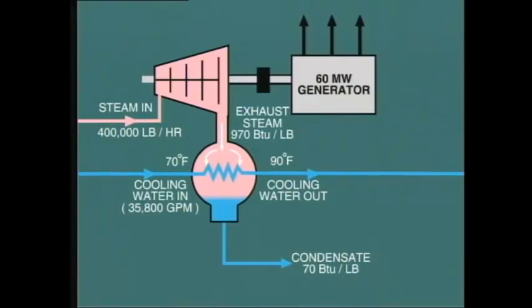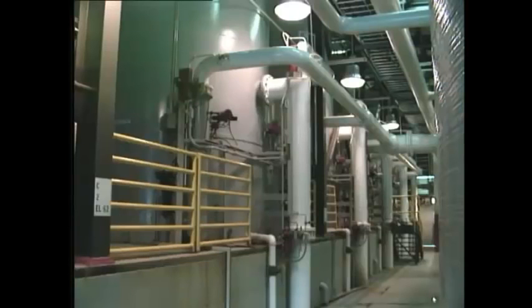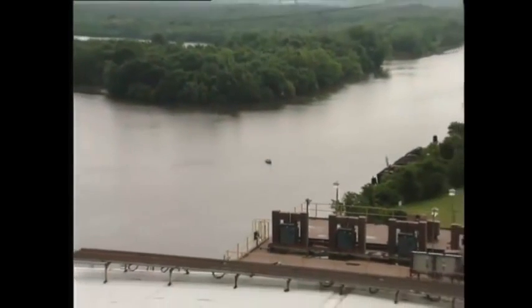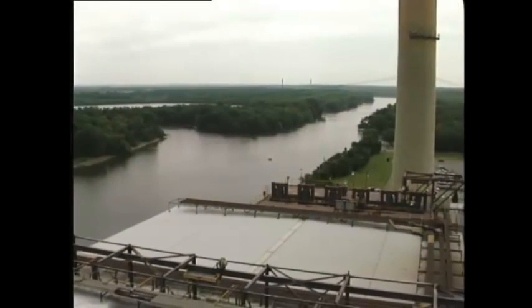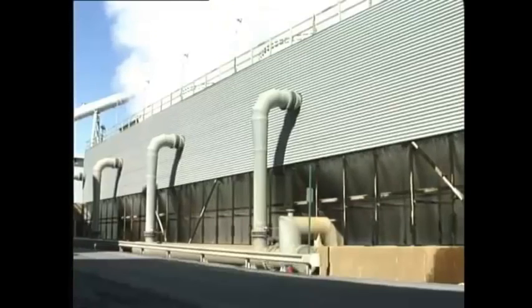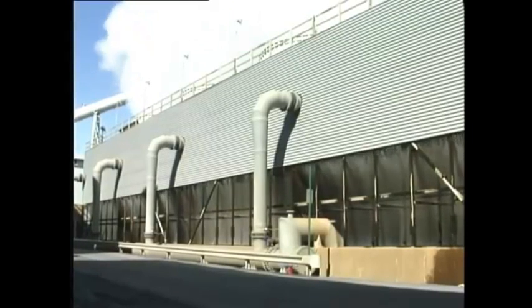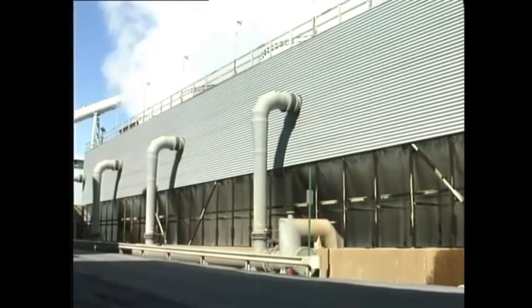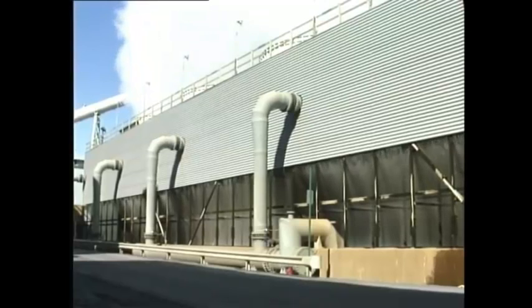In order to condense steam into water, all of the latent heat must be removed. That is about 970 BTU per pound. In order to achieve this, a very large quantity of cooling water is required. For example, a 60 megawatt unit may require as much as 35,800 GPM of cooling water to pass through the condenser. Such a large quantity of water cannot be supplied by a water treatment system. Therefore, the condenser cooling water, or circulating water as it is known, is normally taken from a nearby river or lake or even the sea. In some cases, a closed circuit system is installed using a cooling tower. We'll be talking more about the actual circulating water system and its components later in this program. For now, we're concerned with the condenser and other vacuum equipment.